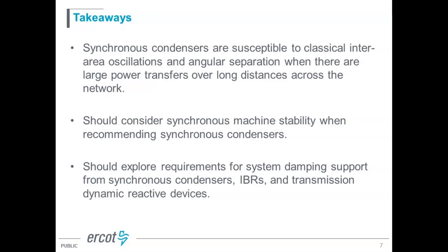Then the other nickel I'll toss out, because this could be news to a lot of people on the call. I'm always harping about inertia not being your friend, but there are times when inertia is your friend. It is my understanding that at least two of those new condensers in South Australia have flywheels or inertia-enhanced condensers. So they have an H constant on the order of 8 instead of 1. Huge inertia. That's a two-edged sword, but in the case of South Australia, it's quite beneficial. That's one of those trade-offs.